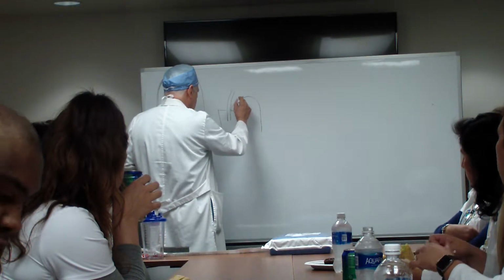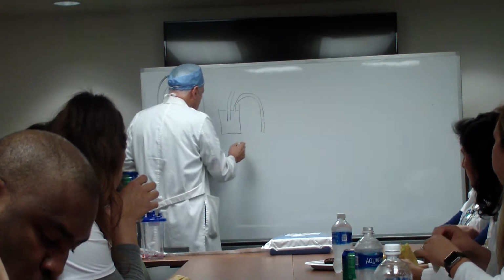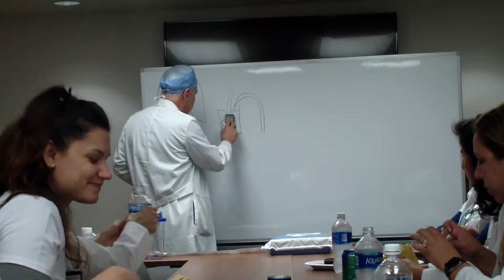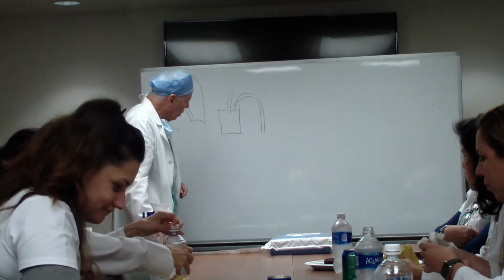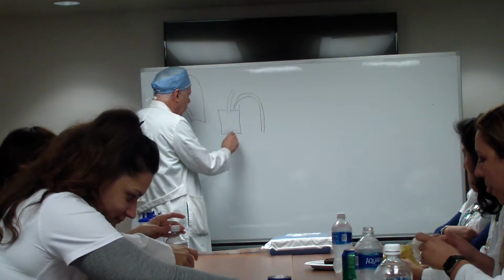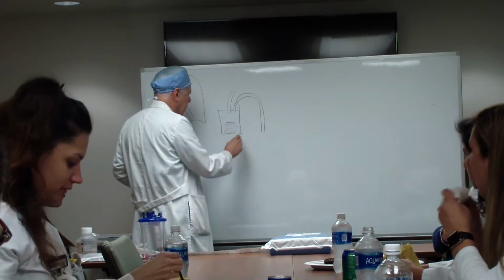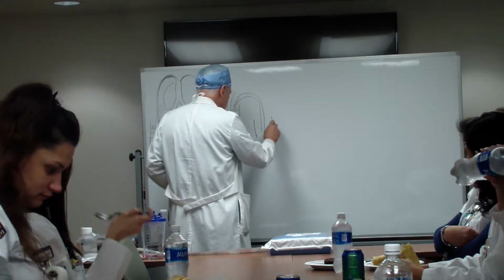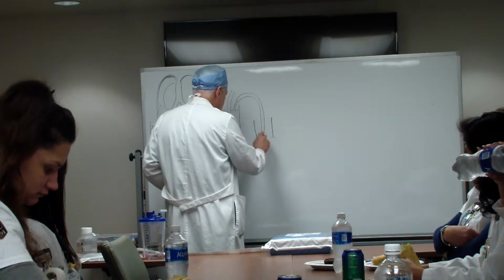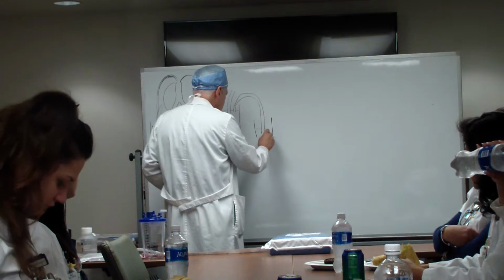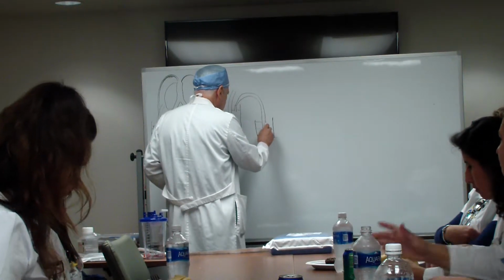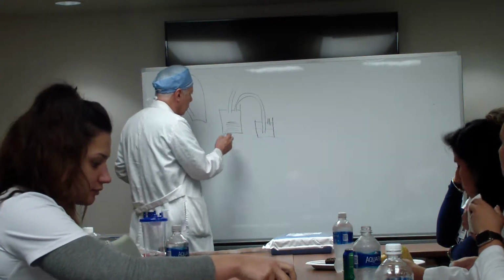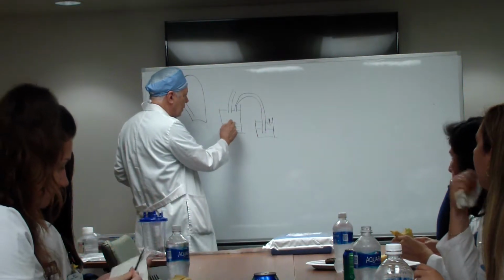So we have this drainage here from the patient, and the fluid that will accumulate here, and then we have an air space here, or there, with a water seal here, and this here. So the fluid will accumulate in this chamber, the air will bubble out here and come out here.